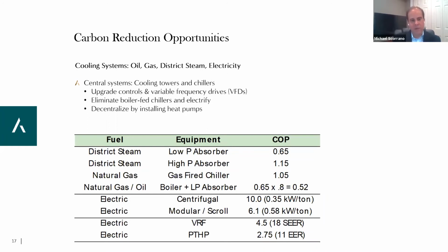If we move to electric chillers - besides the carbon component of how they make electricity - electric chillers themselves have a much higher coefficient of performance. They do much better because with an electric chiller you have a cooling tower, using water which already has energy in it to help dissipate the heat. So you don't need to supply all that energy into the air conditioning equipment to drive the process. It just has much higher efficiency overall, or coefficient of performance.